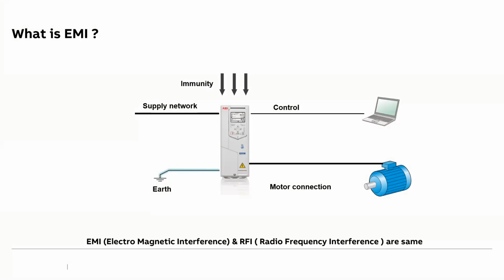So it says that there are two parts. One is the immunity, and another is the emission. So this IEC code says that the product on which this EMC standard is being applied should be immune to EMC or RFI disturbance from surrounding equipment. There are other equipment also in the system which generate these EMCs. So it should ensure that my product is not getting affected by the other EMC being generated by other devices. So basically it is immune. So immunity level is there.